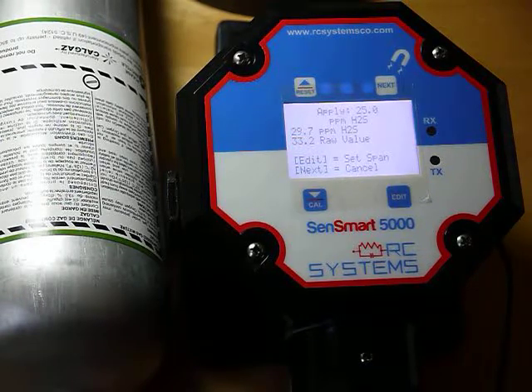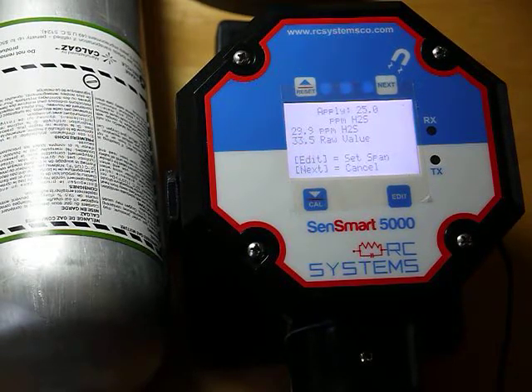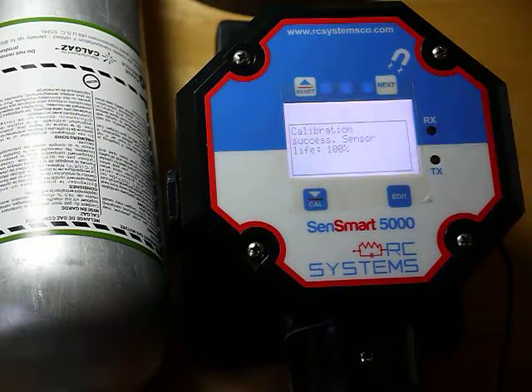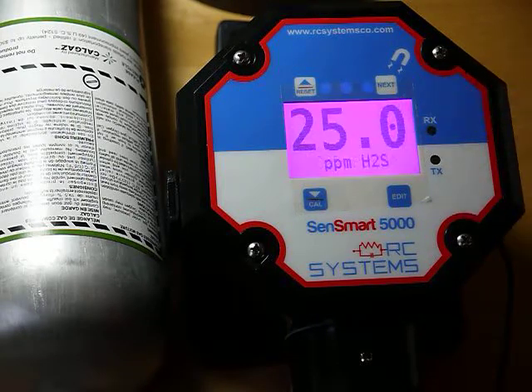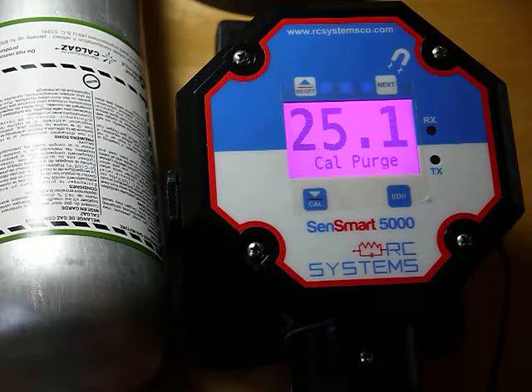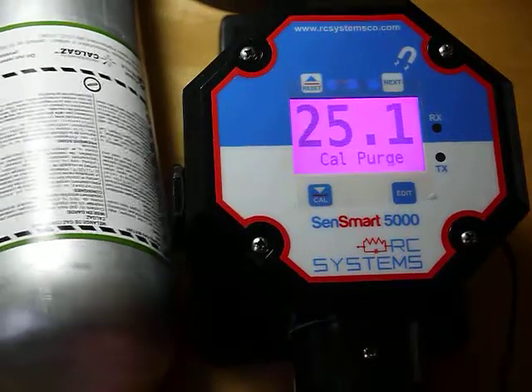So a lot of times the gas detection companies recommend having the gas on for around 2 minutes. That's normally how long it may take a sensor to stabilize. Okay, so I've got 29.9 right now. So I'm going to set that value. Oh, okay, it switched to 30, but basically it's barely moving now. So I hit that. Now it's giving me this sensor life is 100%. So I pull that off, shut the gas off.